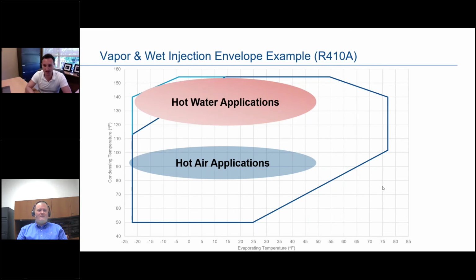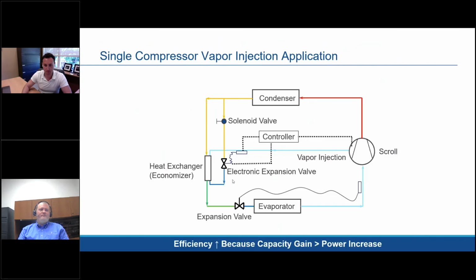All right, great. Next, is a de-superheating valve needed? No, really all you need is a solenoid valve to shut it off, and then an electronic expansion valve. You still need your main expansion valve in there, but we don't need a de-superheating valve in the system. Okay. Then regarding mass flow, the question is, what is the typical percent mass flow and what controls the vapor injection mass flow?